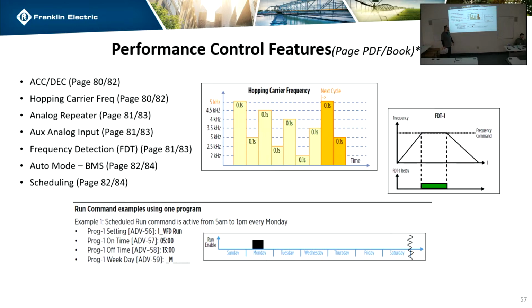I do know that we've had complaints. They'll use VFDs on big boosters for apartment complexes. And those are the people that complain about motor noise, because someone's on the first or second floor next to this gigantic booster and they hear it every time it's on. I've also heard of people having hearing aids and the carrier frequency affects the hearing aids. They'll get a squeal in there, and so you'll have to, basically, I assume this will fix that. Go to the next one.